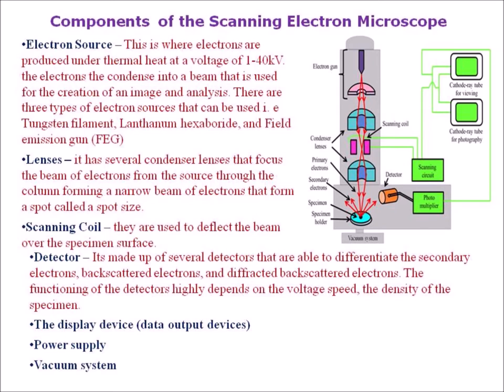Next is the scanning coil, which is used to deflect the beam over the specimen surface. The detector is made up of several detectors that are able to differentiate secondary electrons, backscattered electrons, and diffracted backscattered electrons. The functioning of the detectors highly depends on the voltage, speed, and density of the specimen. Next is the display device, data output device, then power supply and vacuum system.